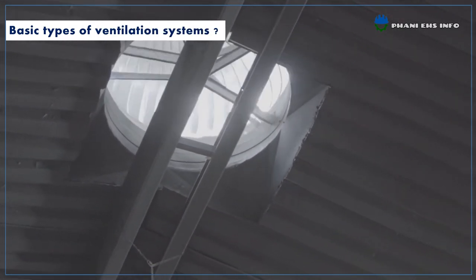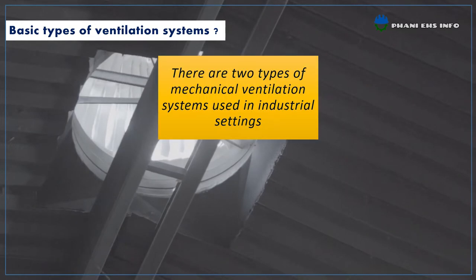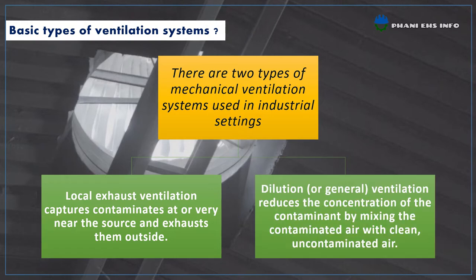Next, basic types of ventilation systems. There are two types of mechanical ventilation systems used in industrial settings. First, local exhaust ventilation captures contaminants very near the source and exhausts them outside. Second, dilution ventilation reduces the concentration of contaminants by mixing contaminated air with clean, uncontaminated air.